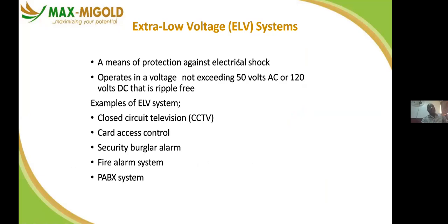We have extra low voltage, ELV. So that's what we say, a means of protection against electrical shock. They operate in a voltage not exceeding 50 volt AC or 120 volt DC that is ripple free. It is not instantaneous. There is no oscillation in terms of alternating current. So it's constant, it's moving constantly. Examples of ELV systems are closed circuit television, that's your CCTV, card access control, security burglar alarm, fire alarm, PABX system, and so on. They make use of this very low voltage.